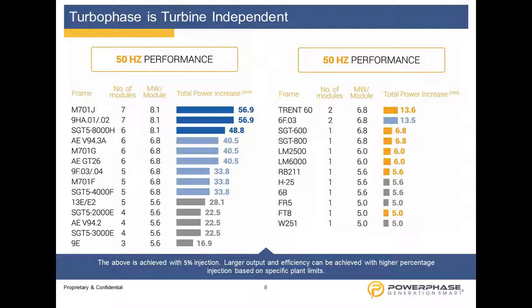The reason we target 5% is most of the owners will recognize that 5% is a common number used by your OEMs for steam injection, wet compression, and as well as NOx abatement water for mass. So all your gas turbines are designed to handle a 5% influx of mass, typically done by the OEMs with water. We're just doing it with dry, clean air.